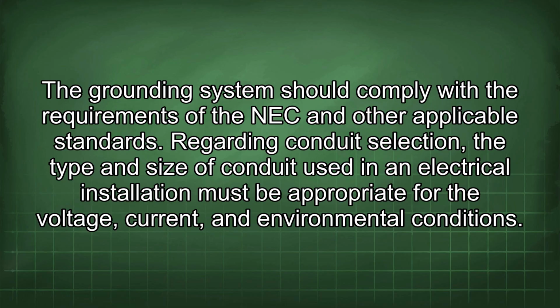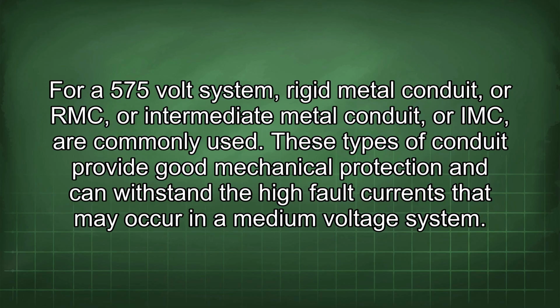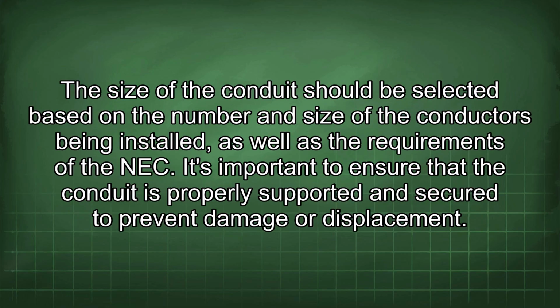Regarding conduit selection, the type and size of conduit used in an electrical installation must be appropriate for the voltage, current, and environmental conditions. For a 575-volt system, rigid metal conduit, or RMC, or intermediate metal conduit, or IMC, are commonly used. These types of conduit provide good mechanical protection and can withstand the high fault currents that may occur in a medium voltage system. The size of the conduit should be selected based on the number and size of the conductors being installed, as well as the requirements of the NEC. It's important to ensure that the conduit is properly supported and secured to prevent damage or displacement.